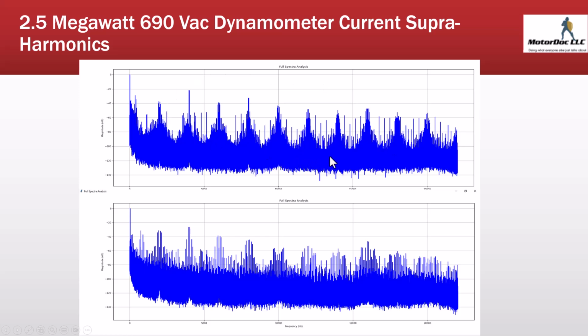Now, the actual current levels are relatively low, and that's where the debate lies, because some of those peaks are high enough that they will block current flow through shaft brushes while also turning the grease in a bearing into a conductor, meaning that shaft brushes will not resolve the issue, and you end up with the problems, failed bearings due to shaft currents, regardless.